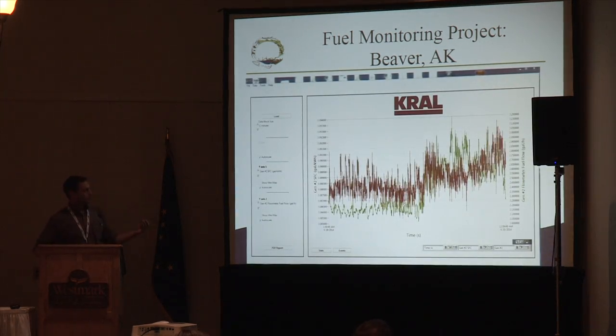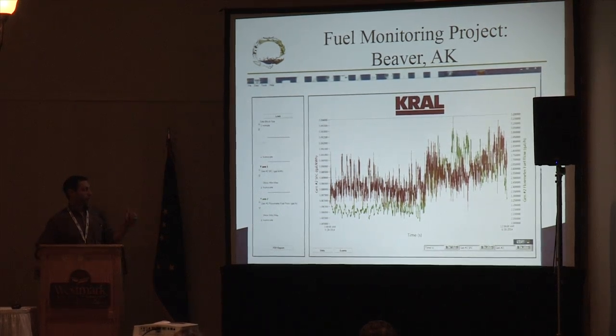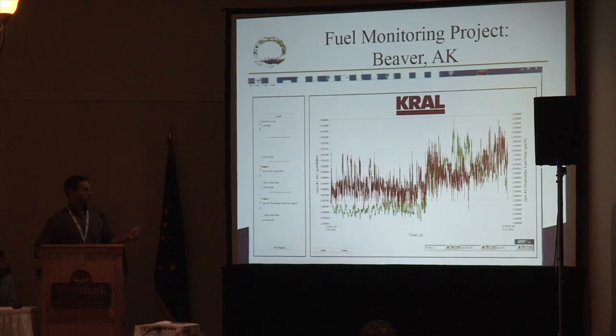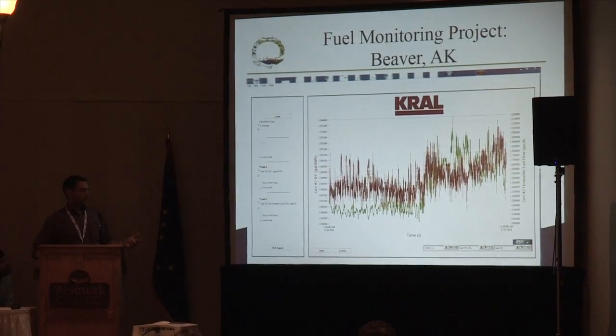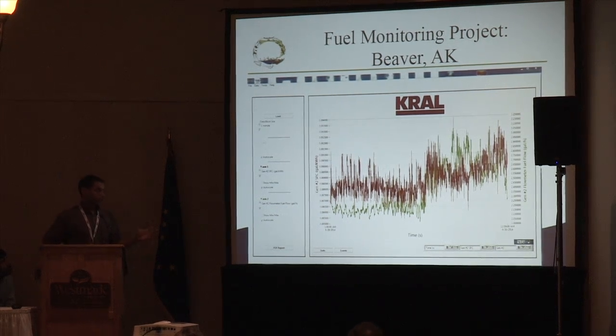This is a printout of what the Coriolis flow meters give us over time, I believe at 10-second intervals throughout the day, maybe even more defined, possibly down to 1 second. I'm not 100% sure — I was hoping to have more time to process the data before this presentation, but time is something they don't have a lot of right now. Basically we get daily updates comparing the draw, or load, in the community to the average fuel flow. The Coriolis flow meters are accurate to about 0.1%, or maybe 0.01%. They measure on the supply and return side of the fuel flow and also correct for temperature.